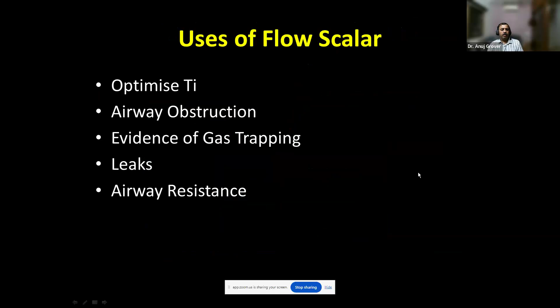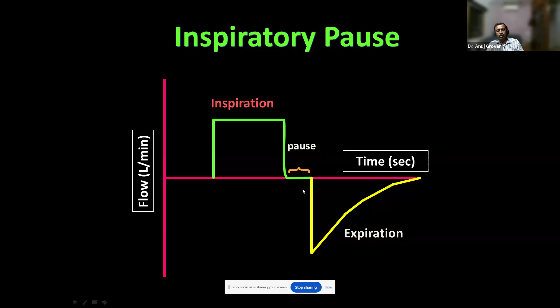So let's look at a few examples. In this example, you can see the flow went up, the inspiratory flow has reduced, but the exhalation hasn't started. So there is a pause, which is called the inspiratory pause. The baby has taken a breath but is not able to exhale. The inspiration has ended, but the exhalation has not started. This is wasted time, and the baby is not really going to like it, so you want to avoid that inspiratory pause. This is because you've set the inspiratory time too long. So what you need to do is reduce the inspiratory time so that there is no pause like this.